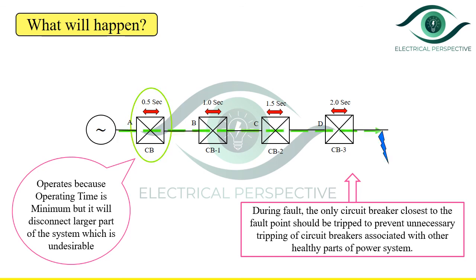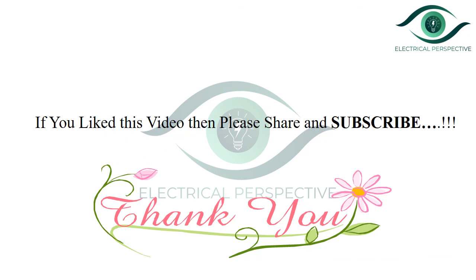We need to follow the basic rule: the relay nearest to the end of the line should have the minimum time setting, and the time settings of other relays should successively increase towards the source end. The drawbacks we have seen can be overcome by incorporating the current grading principle in addition to the time principle, which we will discuss in the next video. This is all about the time graded system. If you like this video, please share and subscribe. Thank you.